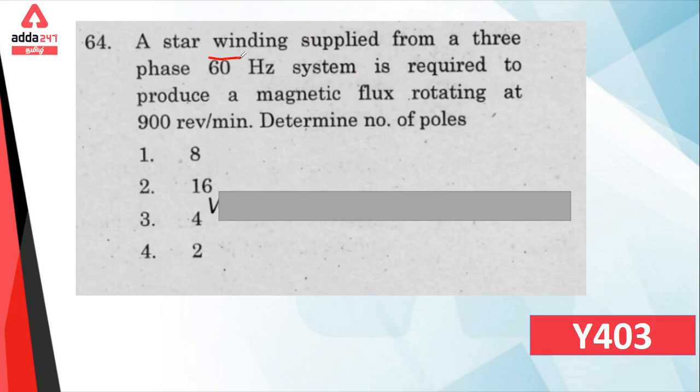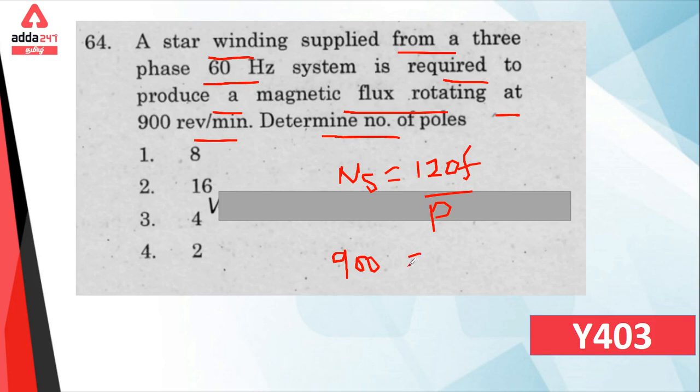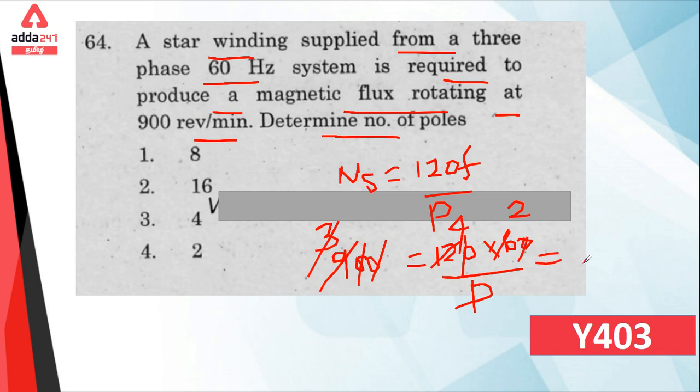A star winding supplied from a three-phase, 60 Hz system is required to produce magnetic flux rotating at 900 RPM. Number of poles? Simple. The synchronous speed is 120f/p. We know synchronous speed is 900, frequency is 60. So 120 times 60 divided by poles equals 900. Solving, poles equal 8.